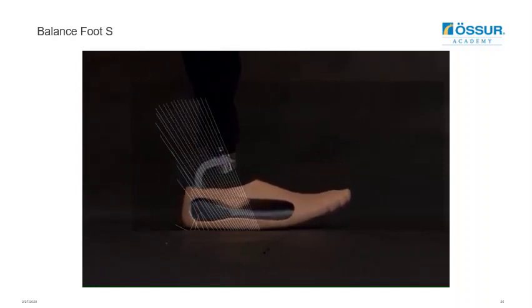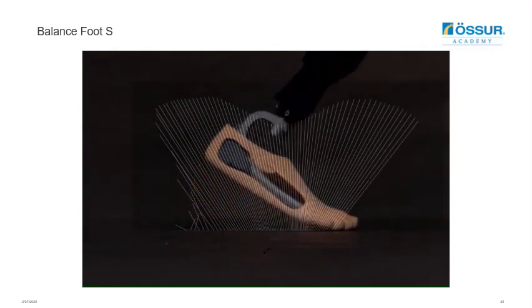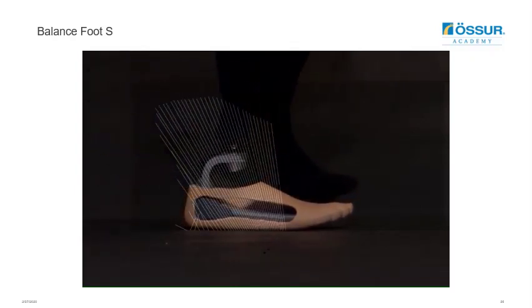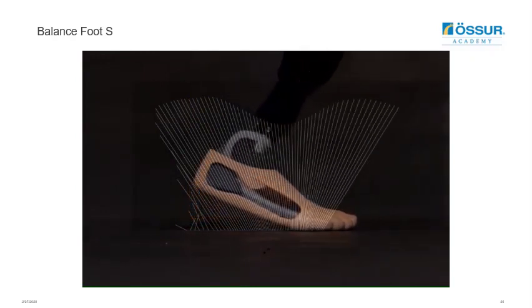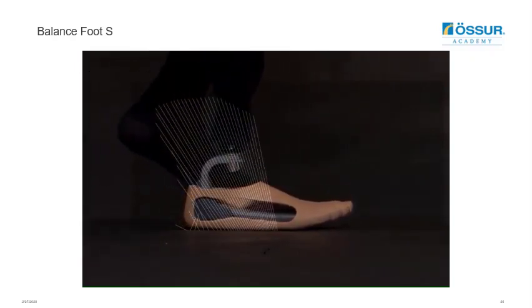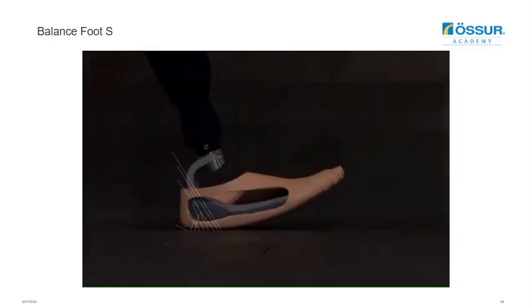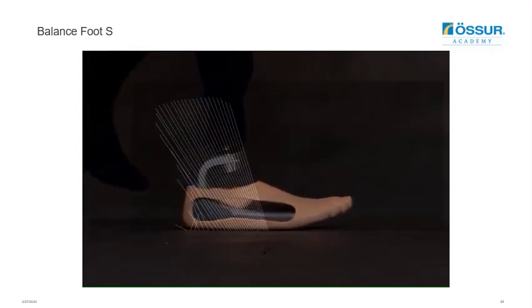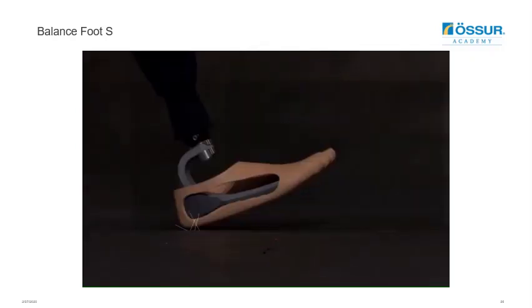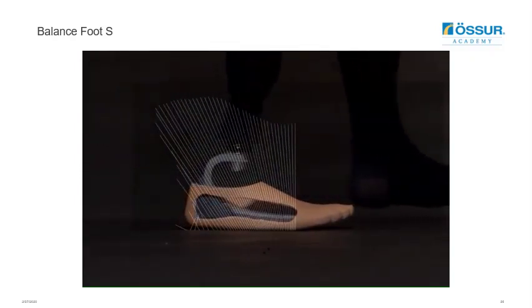Watching this video of the Balance Foot S rollover from heel to toe, note the vertical lines that appear across the screen. These lines represent the amount of loading on the foot and the direction from which that load comes. In early stance, there are longer lines angled in the direction from which the prosthetic user is coming, indicating higher load. In mid stance, the lines become more vertical and slightly shorter, indicating less load coming through the prosthetic foot. Finally, as the patient rolls forward into late stance, the load lines become longer again with a forward lean, indicating that the foot is returning energy to the user in a forward moving direction.